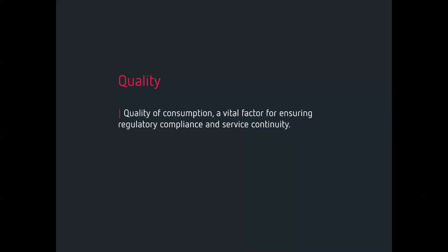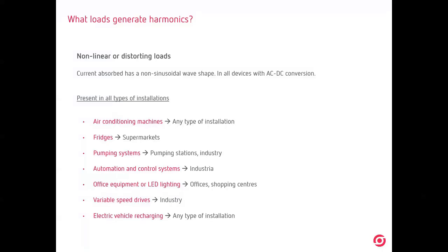Okay, so we have talked about analysis. Now very fast, we'll talk about quality. Quality of consumption is a vital factor for ensuring regulatory compliance and service continuity. So we are going to talk about harmonics very fast because we already made the webinar regarding harmonics. We are able to use harmonic filtering solutions inside the industry because in the industry we have harmonics. Because all non-linear loads are creating harmonics. All the loads that are connected to AC but internally have DC, okay, for being supplied, these will create harmonics. All the devices with AC-DC conversion will create them. Which types?